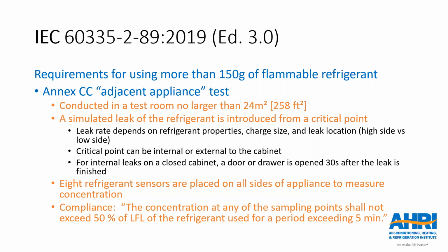The purpose of this test, because an equipment manufacturer does not have any control over the existence of potential ignition sources outside or adjacent to that appliance, is really to simulate a refrigerant leak and measure the concentration of refrigerant around the piece of equipment to ensure that the design is safe. Manufacturers have all the control over the electrical components and things on board, but really nothing outside of that footprint. So that's why this test was created.